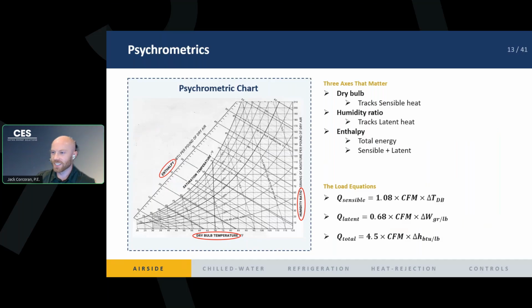So the first thing we have to talk about, right, is psychrometrics. When I first looked at a psychrometric chart, I got dizzy and I never wanted to look at it again. It looks very complicated, and it can be complicated, but for the purposes of today, there's really just some simple trends that we want to look at, right? And so I circled the three axes that we really care about. Our dry bulb temperature is along the bottom. Those are vertical lines. So basically moving left or right, you're changing your sensible heat, right? And so if you just change the temperature and you don't move up or down on this chart, you're only changing sensible heat, and that's the dry bulb temperature.